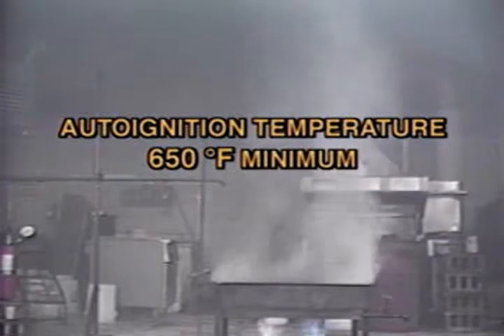This second sequence shows a fire test following the older UL Subject 300 test methods. This less stringent test allows the use of mock-up appliances with no specified heat-up rates, and because the mock-up appliances are not insulated they cool down very rapidly. Also, the required minimum auto-ignition temperature of the cooking oil is 650 degrees Fahrenheit, versus 685 with the new standard.